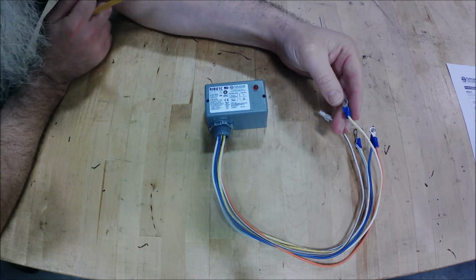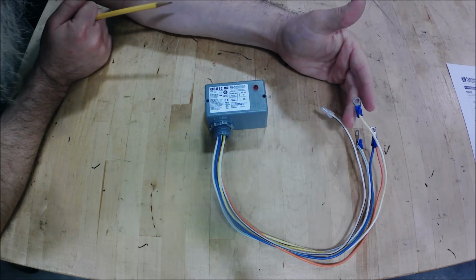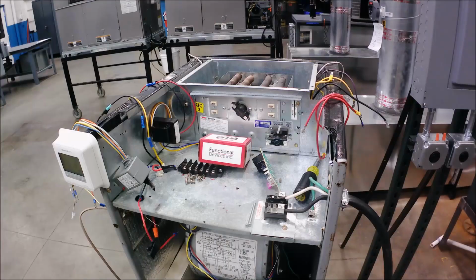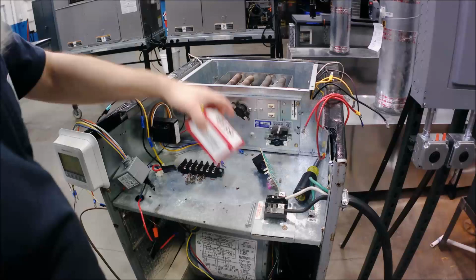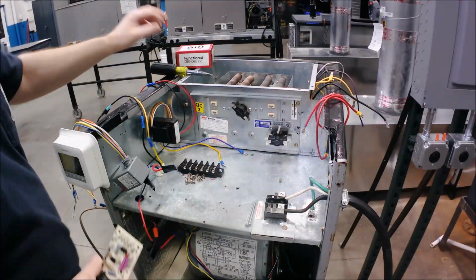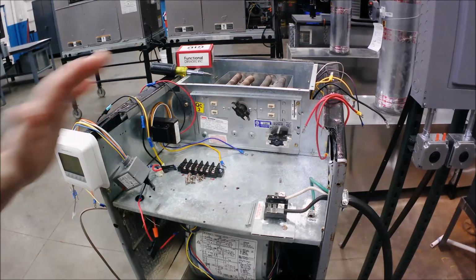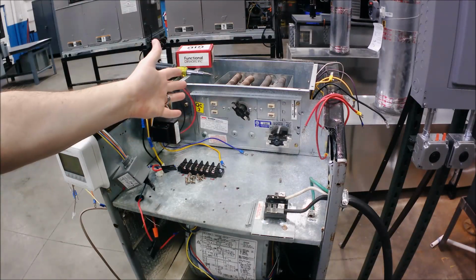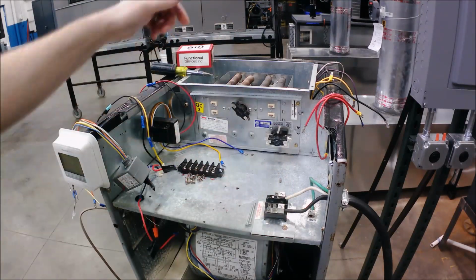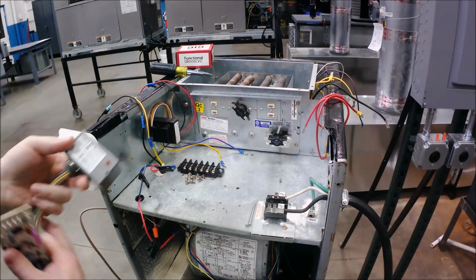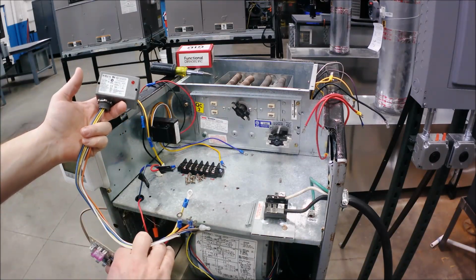And you'll see that we're going to put a terminal block in just to try to keep it neat so we can do some voltage checks. All right, so we know we're putting in a RIB relay. Here's our standard air handler. Let me get all this junk out of the way. I've got some wires hanging over the side because we're going to rewire the heat strips in here from the terminal block.